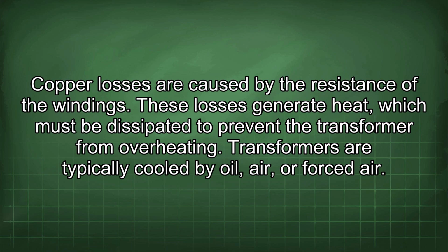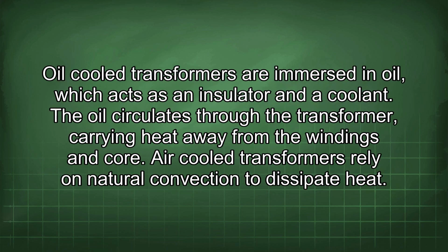Transformers are typically cooled by oil, air, or forced air. Oil-cooled transformers are immersed in oil, which acts as an insulator and a coolant. The oil circulates through the transformer, carrying heat away from the windings and core.